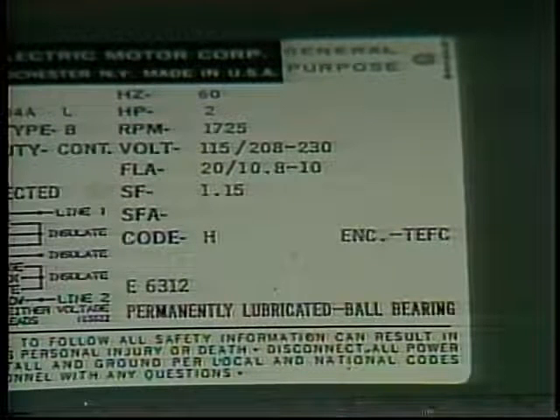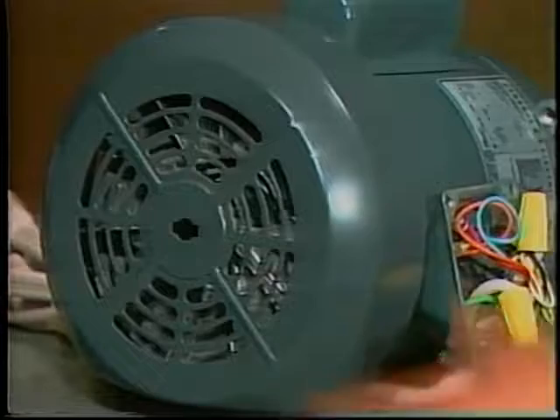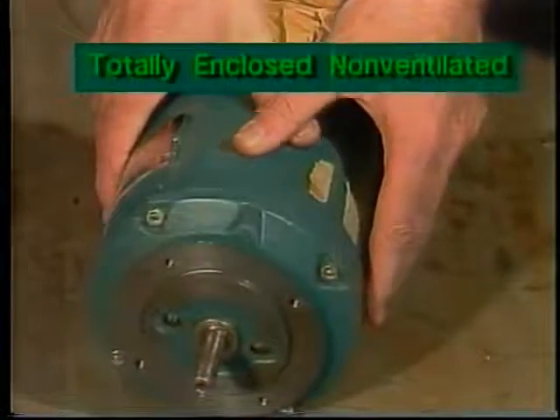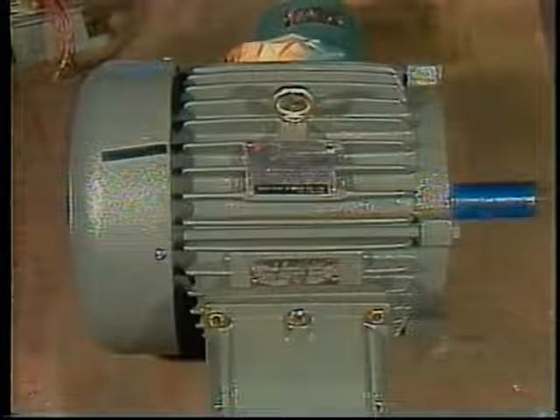In dirty or wet environments, a totally enclosed motor should be used. This is a totally enclosed fan-cooled motor — instead of pulling air through the motor, the fan blows air over the outside of the motor housing. Without the fan, a totally enclosed motor is non-ventilated and relies on air convection to carry heat away from the housing. Totally enclosed motor housings often have ribs or fins on the outside to improve heat transfer. Totally enclosed air-over motors are intended to be mounted in an air stream for cooling — fan and blower motors are often of this type. Explosion-proof motors are used in hazardous atmospheres. They are totally enclosed motors with an especially rugged housing designed to withstand an internal explosion of a particular vapor or gas without rupturing or touching off a general explosion. An explosion-proof motor can't be used anywhere.